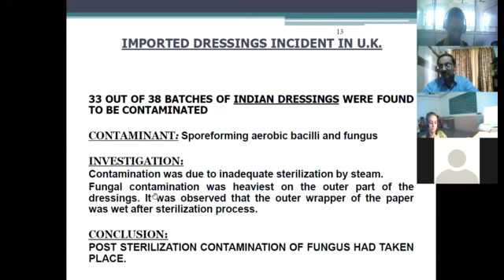So you stop the steam in the chamber, but you continue to have steam in the jacket. So the moist dressings become dry. Then only you stop the cycle and you remove the dressings. So that is how care has to be taken. If that is not done, some such issues can happen and your whole batch can become non-sterile.